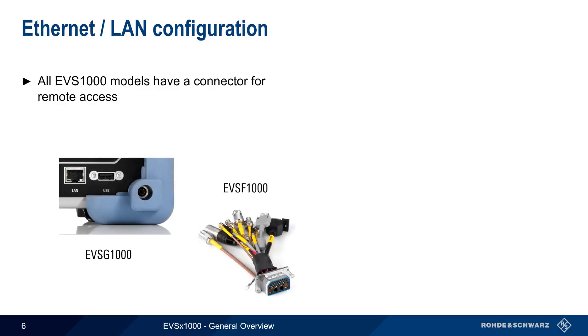All versions of the EVS have a LAN connector which can be used for remote access. On the EVSG, an Ethernet connector is located on the rear of the instrument. On the EVSF, the fan-out connector contains an Ethernet jack as well. EVS-D models use wireless LAN for their network connection. In all cases, either fixed or dynamic IP addresses can be configured. Once a LAN connection has been configured, the EVS graphical user interface can be both viewed and controlled via VNC, a widely used, free application.